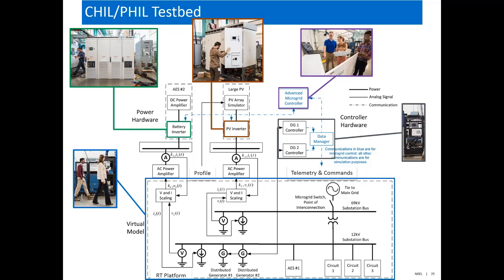The results we got were very interesting. We were able to do a lot of testing that's just not possible in the field, like incurring multiple power outages on the community, pushing their voltage way above 1 per unit, and changing the frequency far above and below 60 hertz. A lot of things that, if I did that in Borrego Springs, I'd be in jail right now.